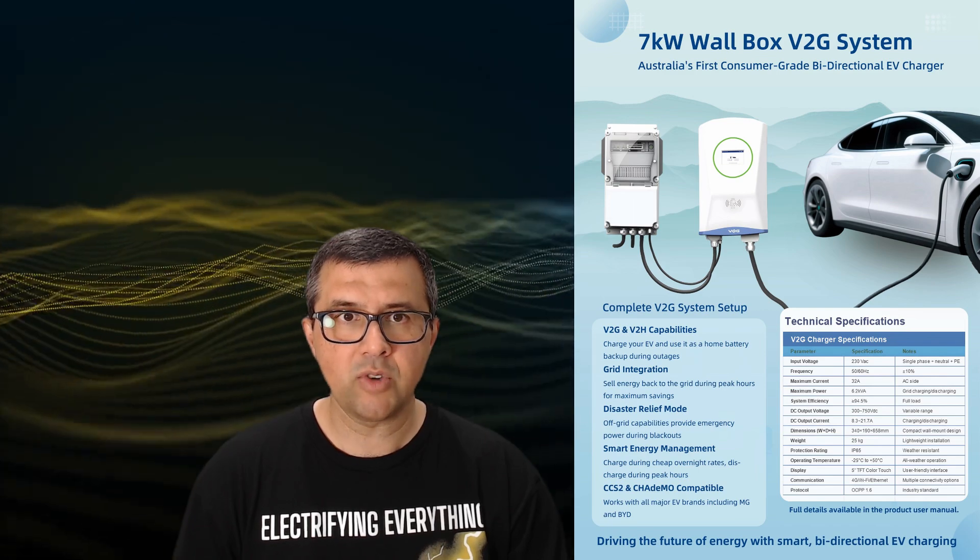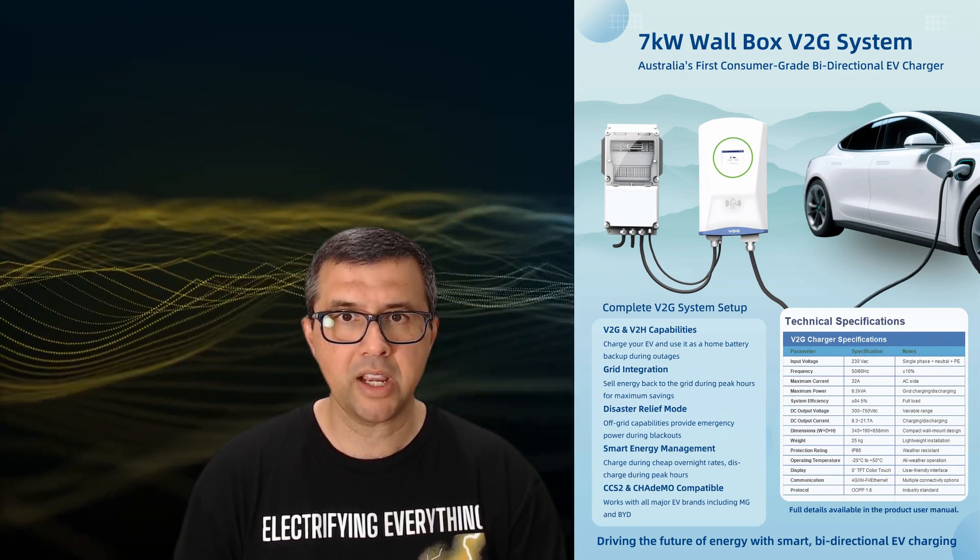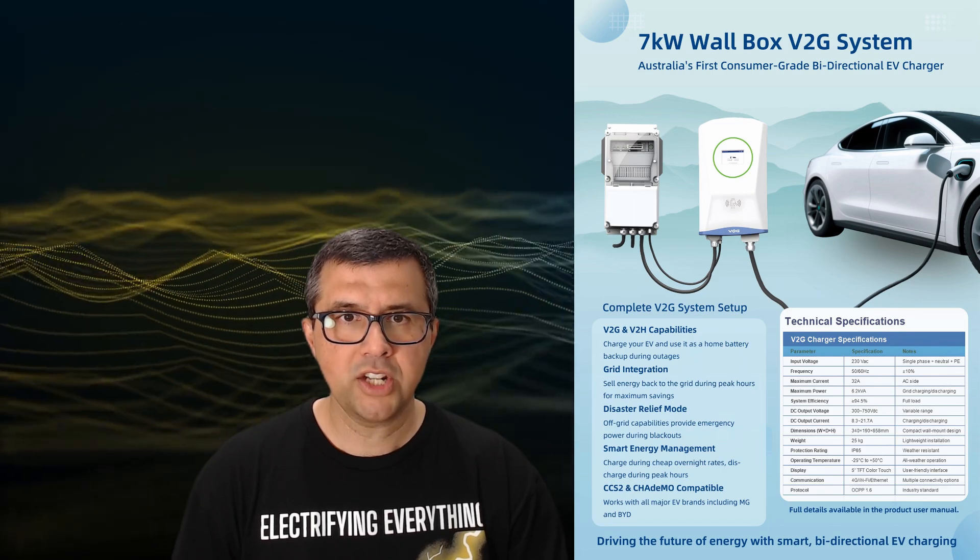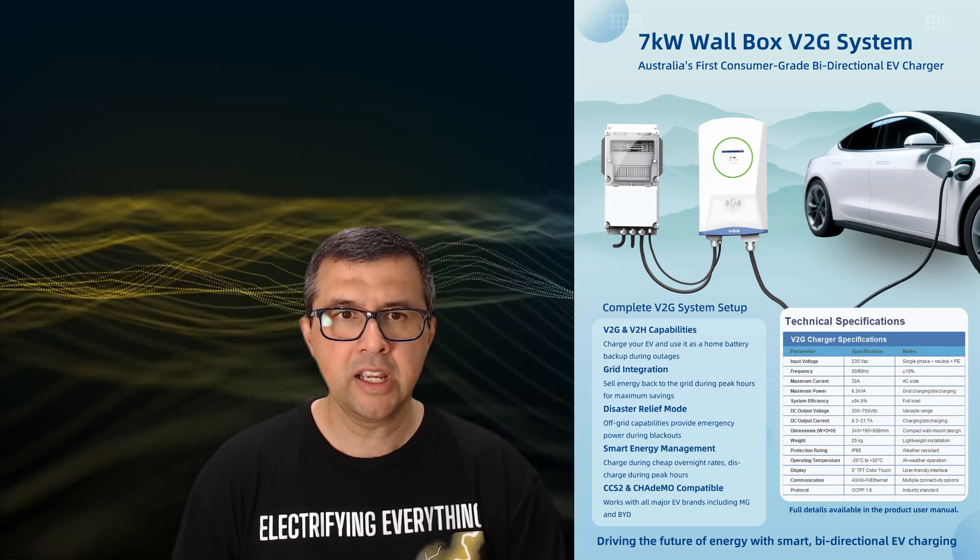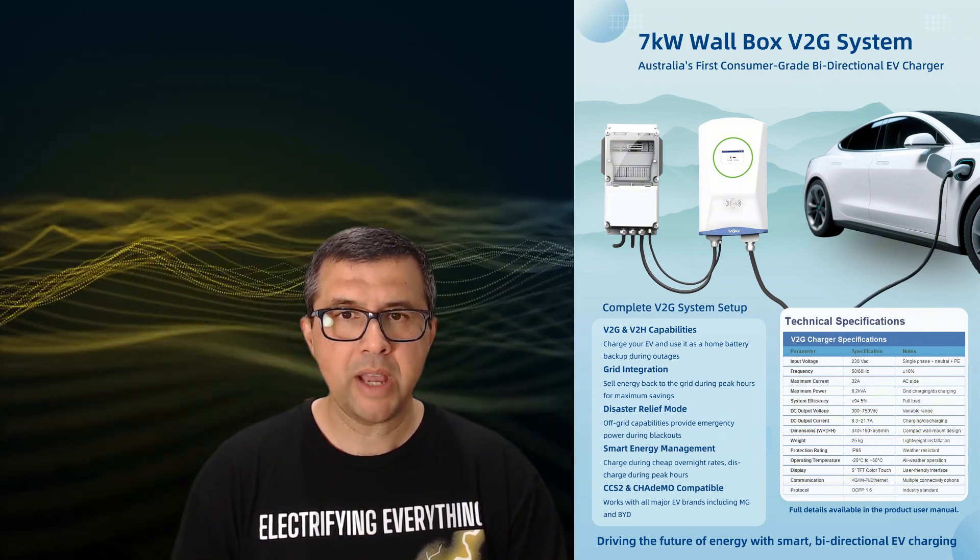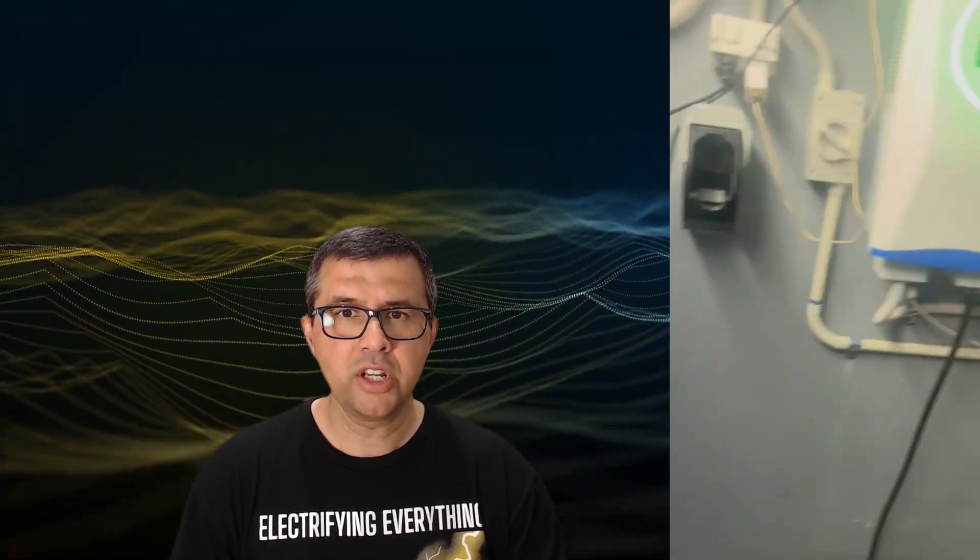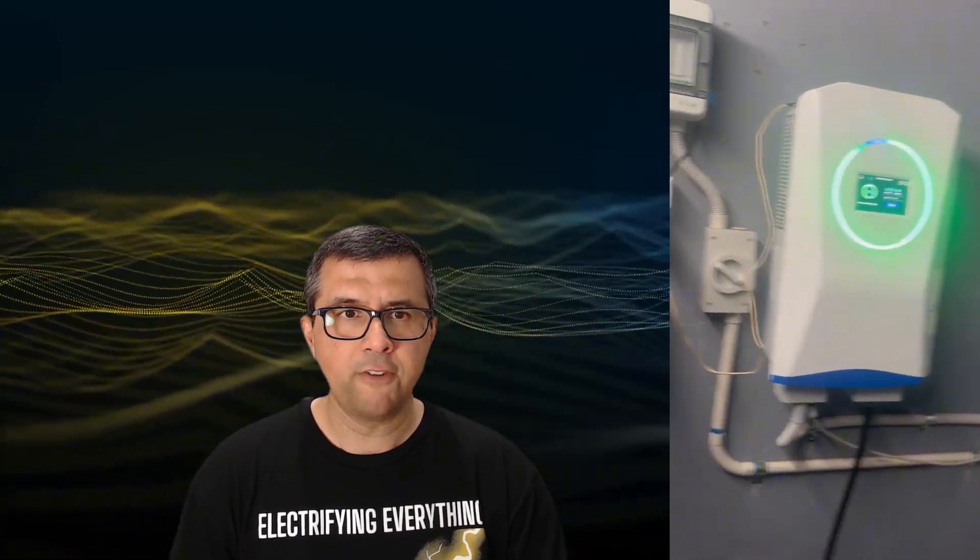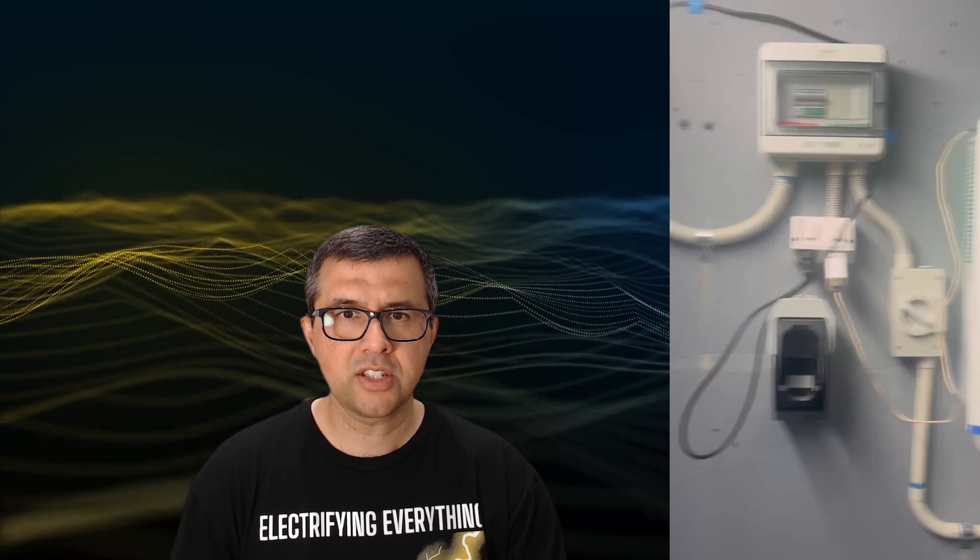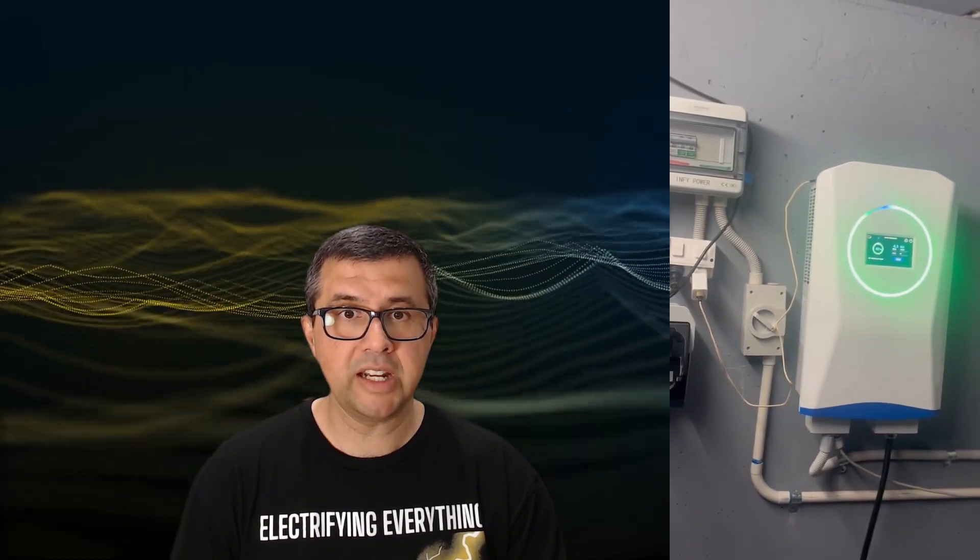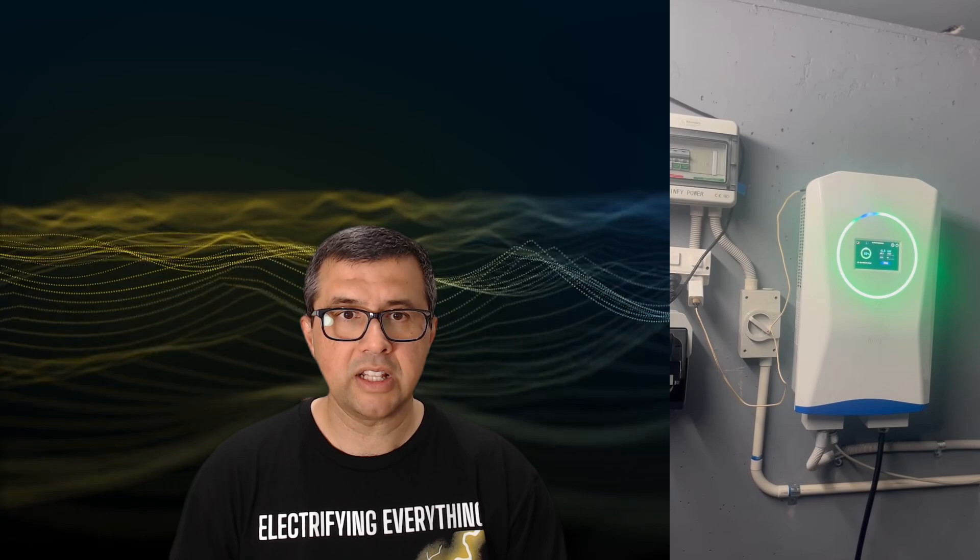Off-grid tests used an isolated load connected directly to the V2H box to emulate household backup. The test method for each EV followed a five-stage sequence: on-grid charging from the building supply, on-grid discharging exporting power back to the building, off-grid discharging powering an isolated load, on-grid to off-grid transition switching from the building supply to an isolated load while discharging with backup mode enabled, and finally an automation sequence—a seven-minute program alternating charging and discharging with power steps at 4 kilowatts and 5 kilowatts.